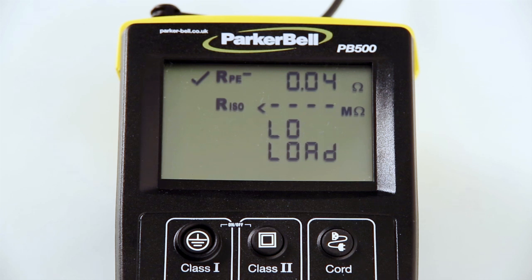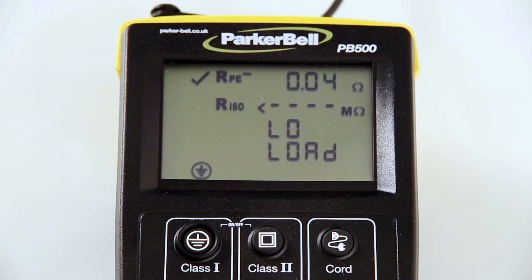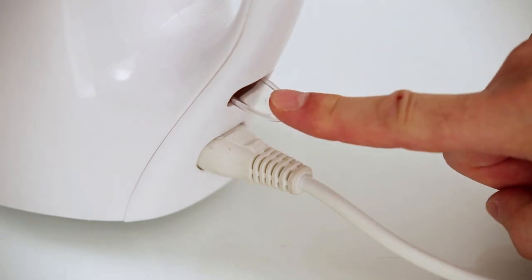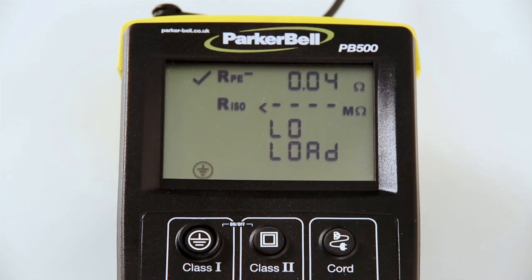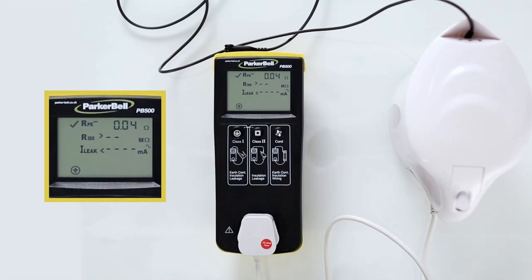Low load is displayed when the appliance power on/off switch is in the off position or the appliance does not have a switch. Turn the switch to the on position and the test sequence will continue. If it doesn't have a switch, press the Class 1 button again to start the test sequence.